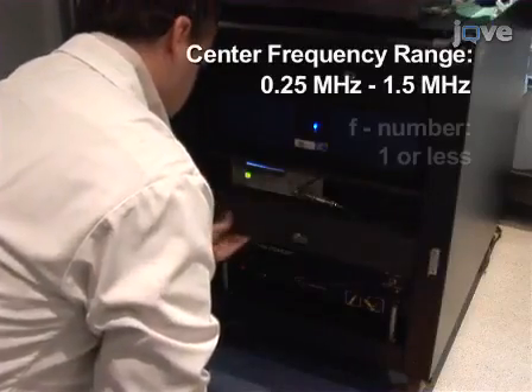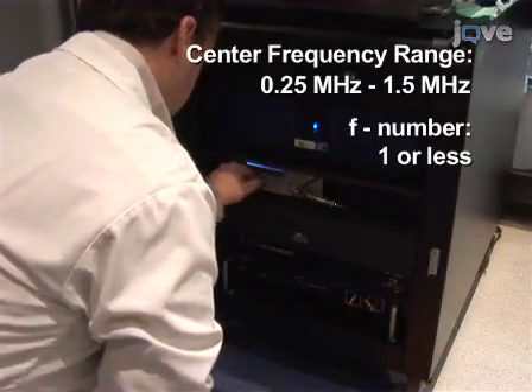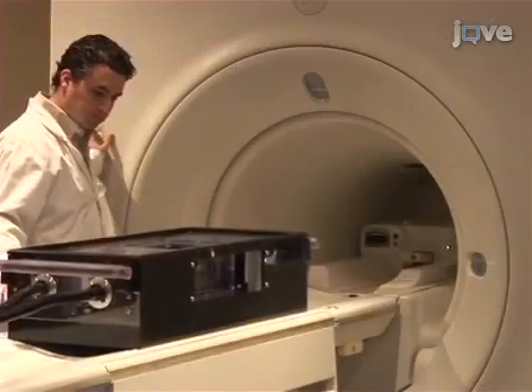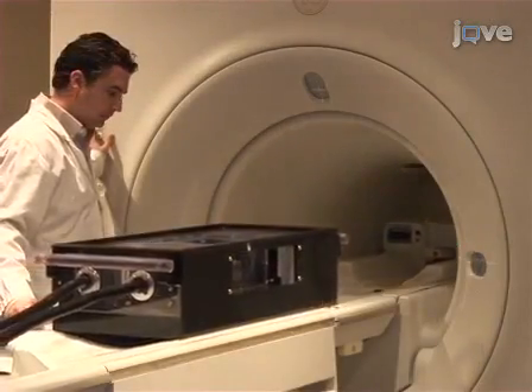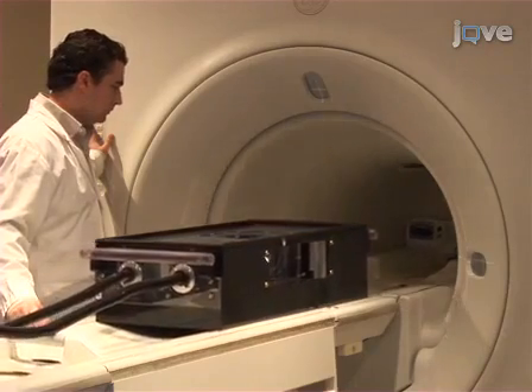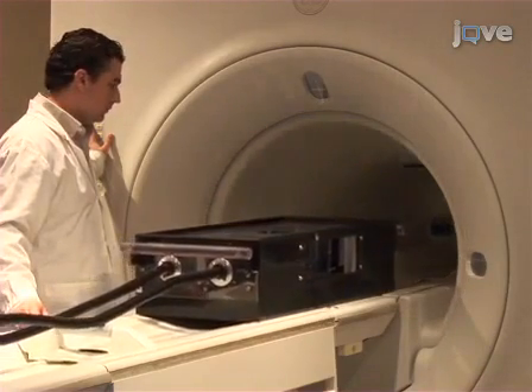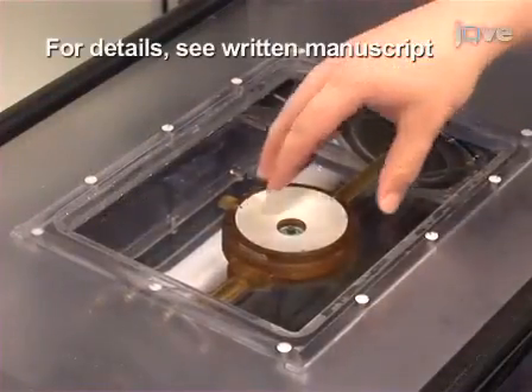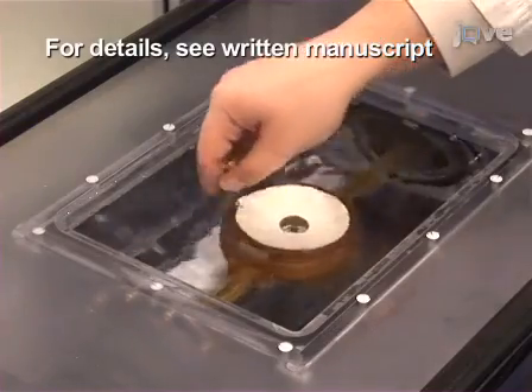Select an appropriate calibrated ultrasound transducer. Next, place a water bath filled with degassed, deionized water on the bed of a 1.5 Tesla or 3 Tesla MRI. Mount the ultrasound transducer in the tank on an MRI-compatible 3-axis positioning stage or system.